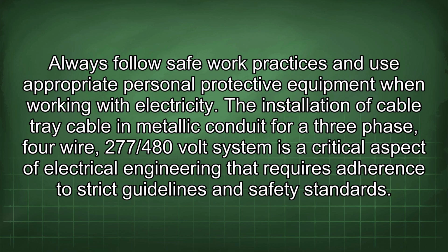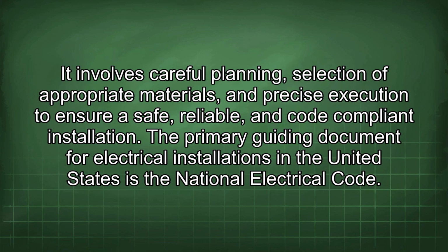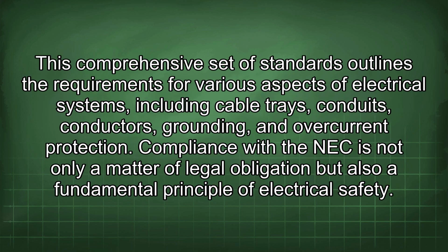The installation of cable tray cable in metallic conduit for a 3-phase, 4-wire, 277/480 volt system is a critical aspect of electrical engineering that requires adherence to strict guidelines and safety standards. It involves careful planning, selection of appropriate materials, and precise execution to ensure a safe, reliable, and code-compliant installation. The primary guiding document for electrical installations in the United States is the National Electrical Code.